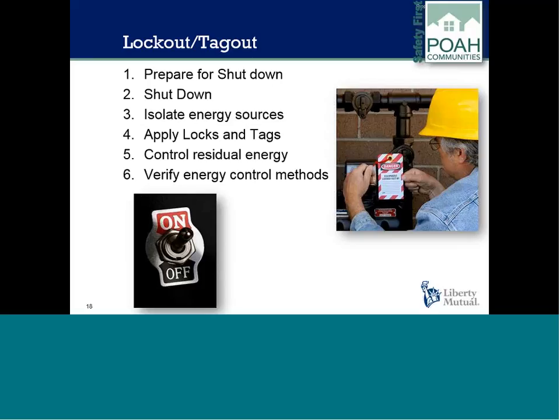Using energy isolating devices appropriate for the energy source, such as manually operated circuit breakers or electrical disconnects for electrical energy, valves for pneumatic energy, or blocking or bars for mechanical energy. All devices must be equipped with a place to attach a hasp or a lock or have a built-in locking mechanism. Step 4, apply locks and tags. Locks are attached so that the device cannot be operated until locks are removed. Devices must be in the off position. Tags indicate that the device and equipment may not be operated.